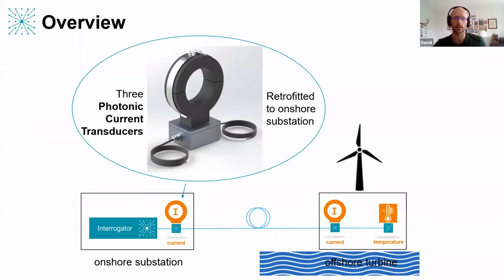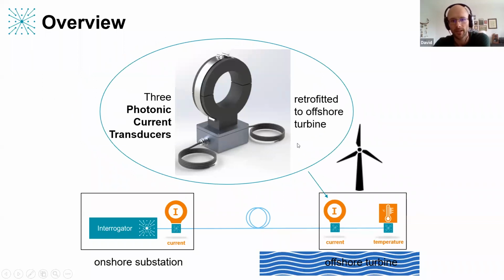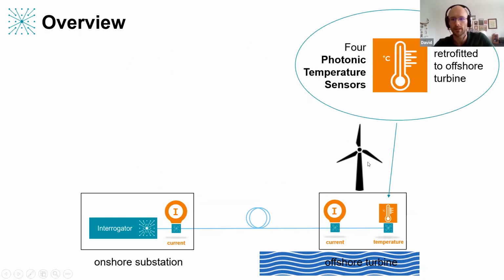So the first sensors are 3 photonic current sensors also installed in the onshore substation to measure currents at one end of the export cable. These are then connected through an optical fiber to another set of current sensors in the turbine, which then enables us to measure both ends of the export cable and allows protection of this cable. Also installed in the turbine are 4 photonic current temperature sensors to measure temperature of the termination points there. So that all these sensors are connected via one single mode fiber to the interrogator, which takes the measurement.